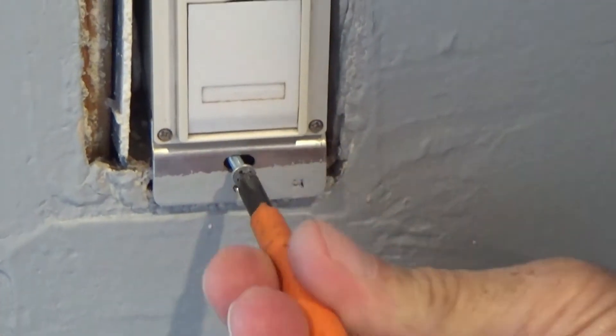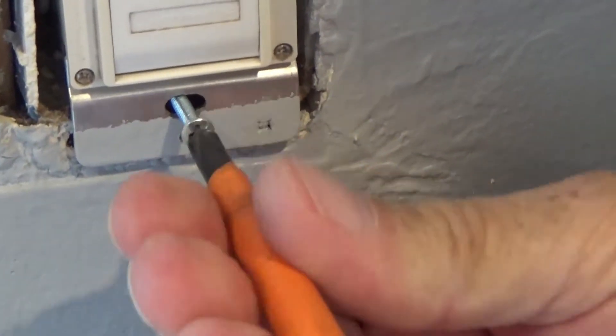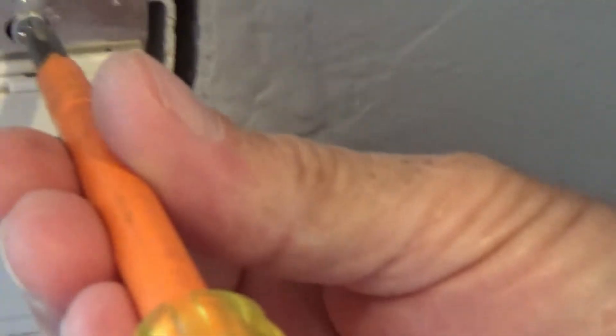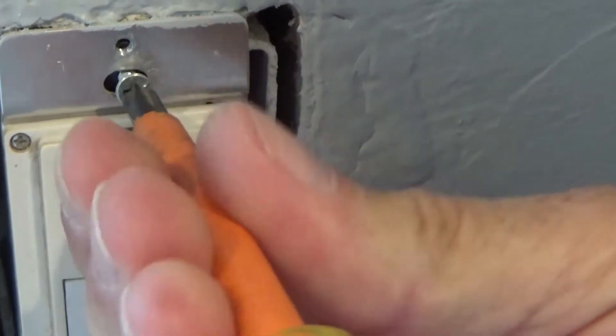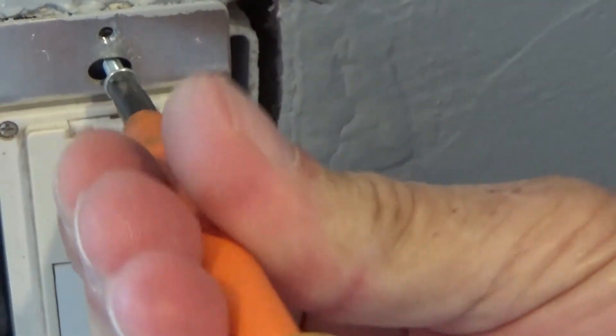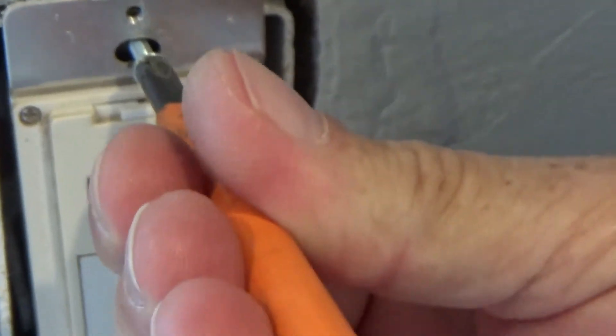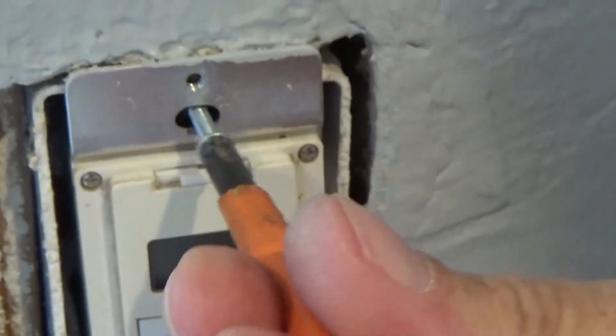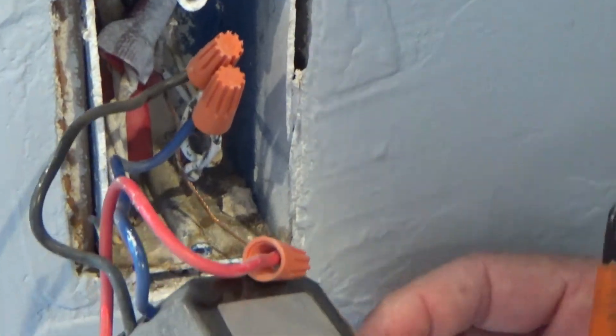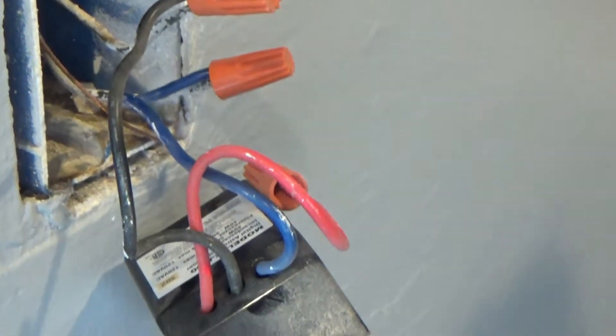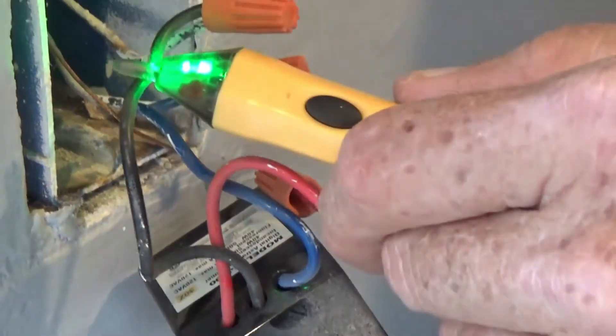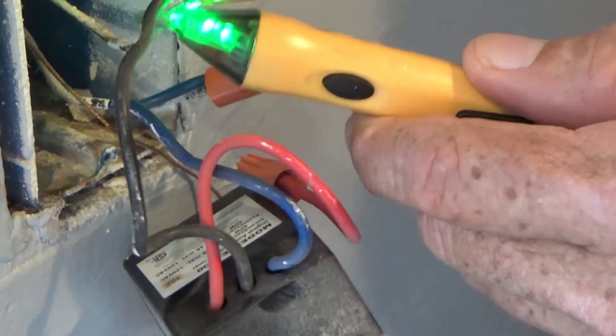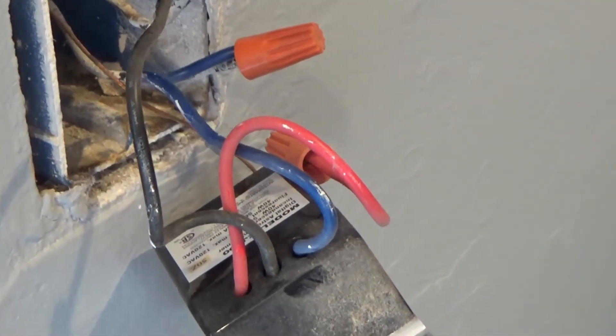Now he's taking out the old switch. If you can, always use an insulated screwdriver - these are rated at 400 volts. Especially if you're working in a breaker box live or even in a switch box live, you really need to have some insulated tools. Okay, no power coming in, so it's safe to undo.